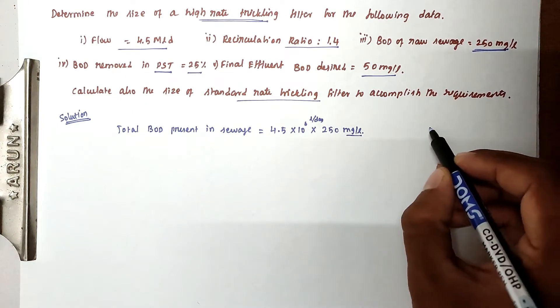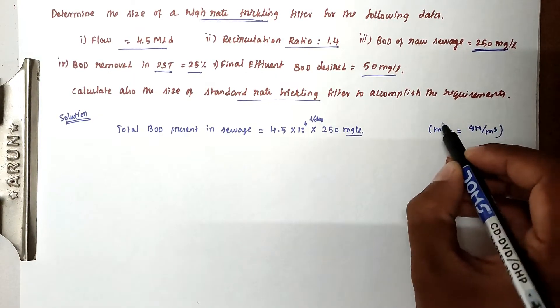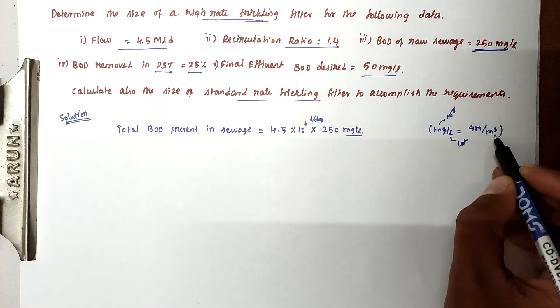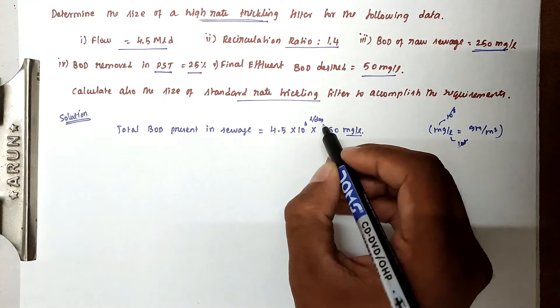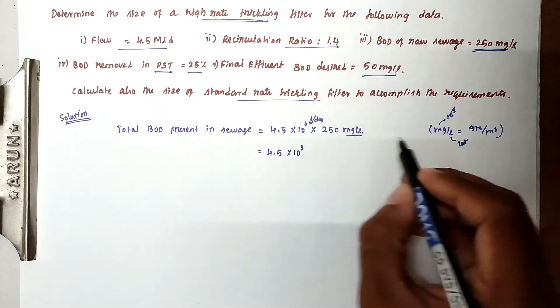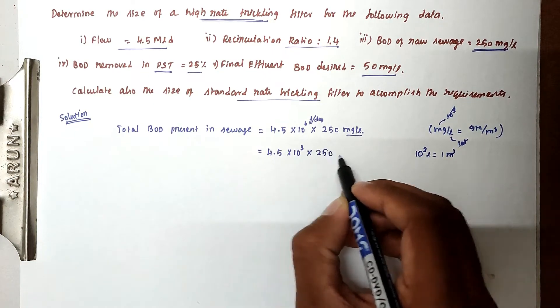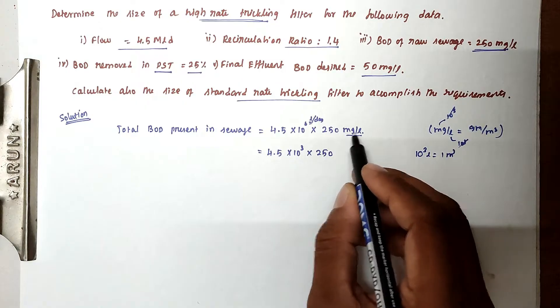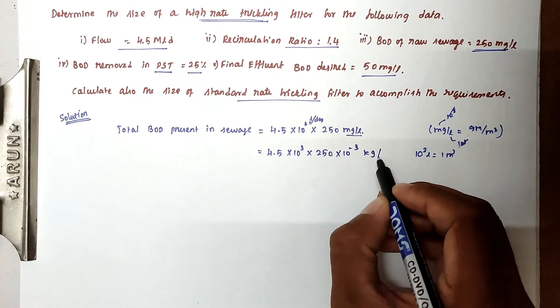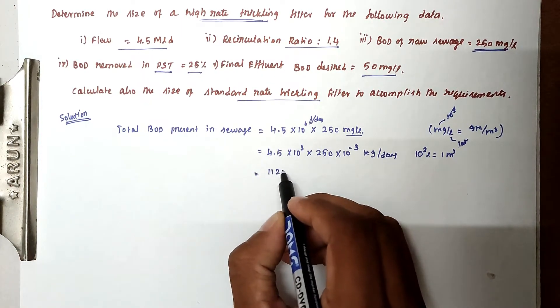Note that milligram per liter equals gram per meter cube, because milligram × 10³ and liter × 10³ to meter cube cancel each other. So converting: 4.5 × 10³ meter cube per day × 250 gram per meter cube × 10⁻³ gives us a total BOD of 1125 kg per day.